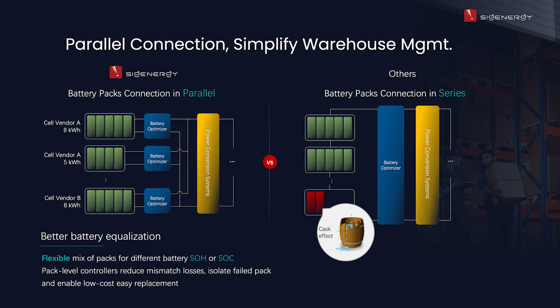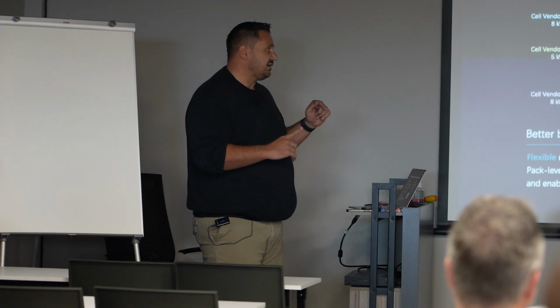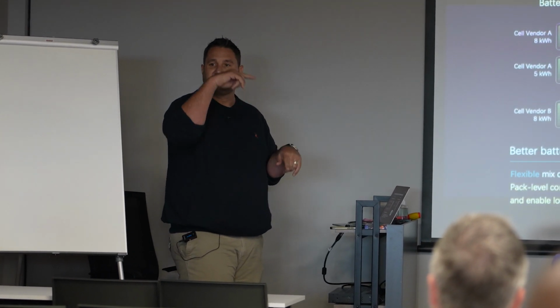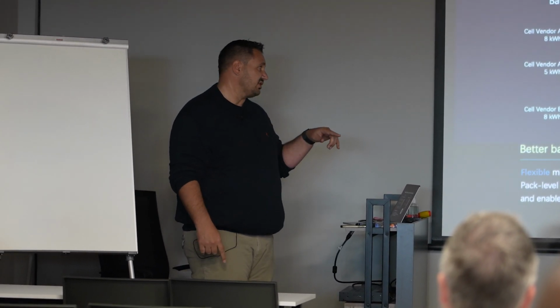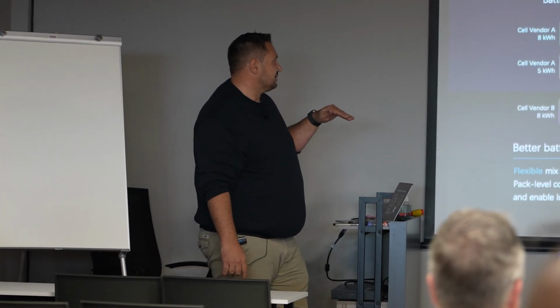Now, what the nice thing is about the way that they connect their batteries is that the battery connection is a parallel connection. So if you stack 6 batteries, all 6 of those batteries are running in parallel with each other, which means that you do not have a series connection, so you do not have the full battery draining into the empty battery.